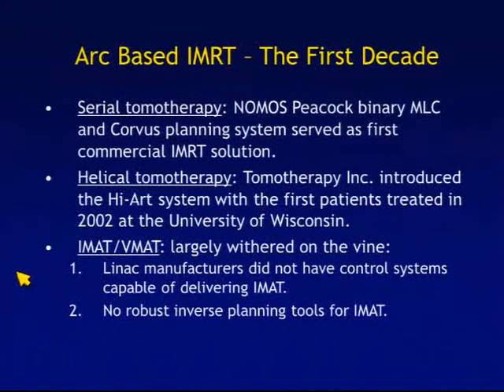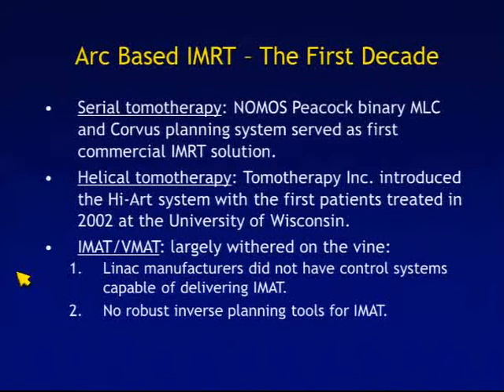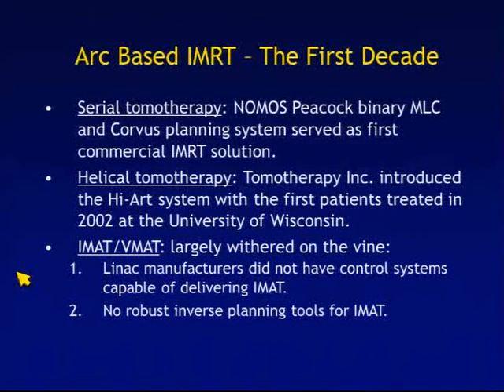Looking at the two decades of rotational IMRT: in the first decade, the first commercial solution was serial tomotherapy, available through NOMOS with the Peacock binary multi-leaf collimator combined with the Corvus inverse planning system — the first commercial IMRT solution. Next was helical tomotherapy introduced by Tomotherapy Inc. with the Hi-Art system, with first patients treated in 2002 at the University of Wisconsin. More recently, Accuray purchased tomotherapy. The IMAT/VMAT technique largely withered on the vine during that first decade, because LINAC manufacturers did not have control systems capable of delivering IMAT, and there were no robust inverse planning tools.